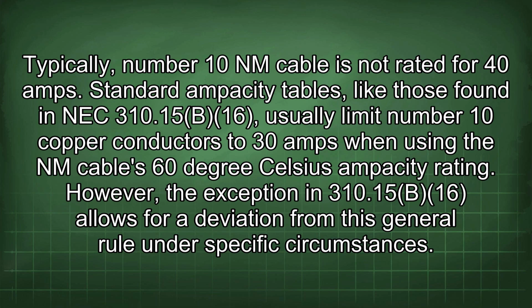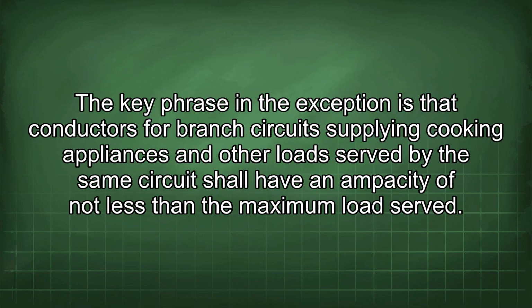Standard ampacity tables, like those found in NEC 310.15(B)(16), usually limit number 10 copper conductors to 30 amps when using the NM cable's 60°C ampacity rating. However, the exception in 310.15(B)(16) allows for a deviation from this general rule under specific circumstances. The key phrase in the exception is that conductors for branch circuits supplying cooking appliances and other loads served by the same circuit shall have an ampacity of not less than the maximum load served.